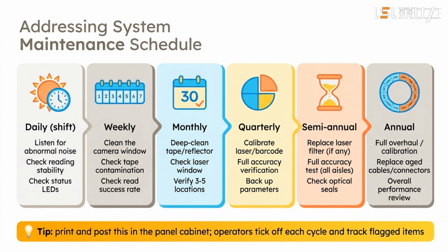This page is the complete maintenance schedule for the addressing system, from daily to annual. Every cycle has defined tasks. Daily, listen for abnormal noise and watch reading stability. Weekly, clean the optical windows and check the tape. Monthly, deep clean and spot check accuracy. Quarterly, full calibration and parameter backup. Semi-annually and annually, full accuracy testing and overhaul.